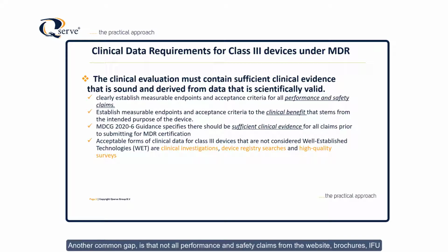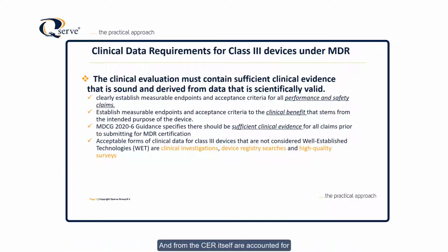Another common gap is that not all performance and safety claims from the website, brochures, IFU, and from the CER itself are accounted for. And in addition, they typically don't have measurable endpoints and acceptance criteria. These are all essential to establishing sufficient clinical evidence.